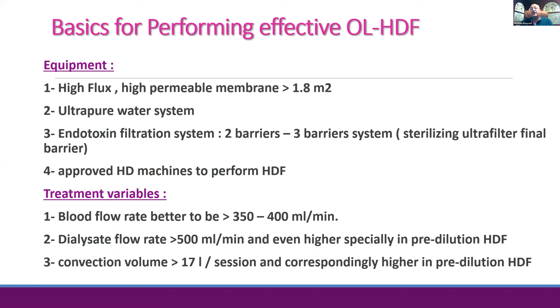The basics for performing effective hemodiafiltration: you need a high-flux dialyzer, more than 1.8, ultrapure endotoxin-free filtration, and approved hemodialysis machines. You need a blood flow of about 350 with dialysate 500, and convection volume from the start above 17 by the Turkish study. Nowadays, it is more than 23, at least by the ESHOL and Spanish studies. So the dialyzer needs to have a defined ultrafiltration coefficient, which should be higher than 40 at least.